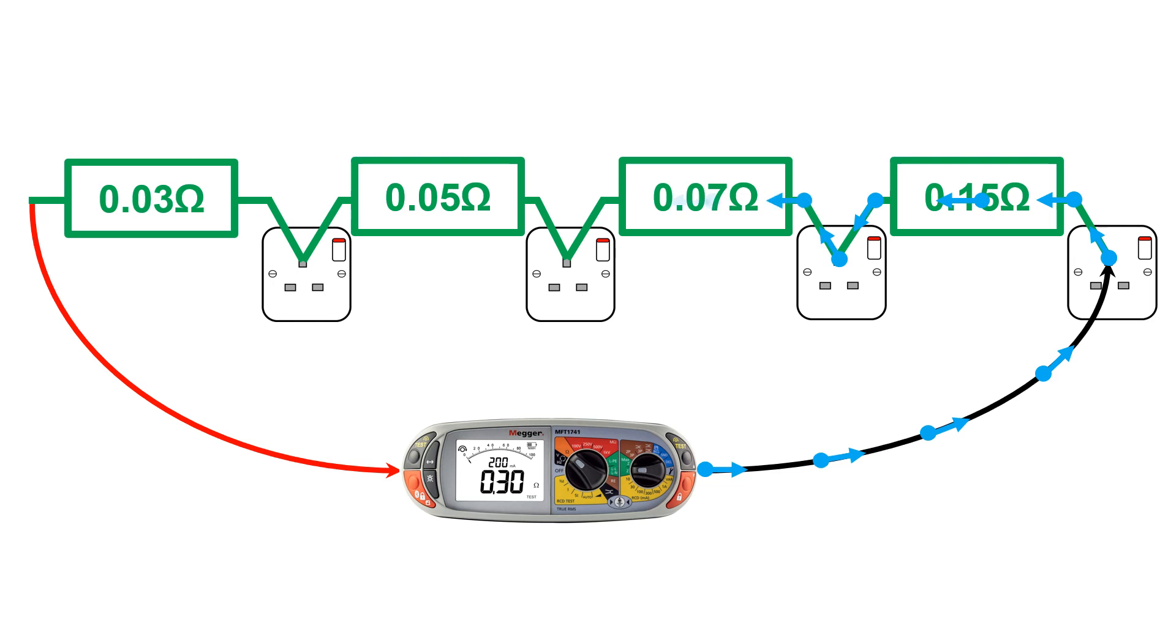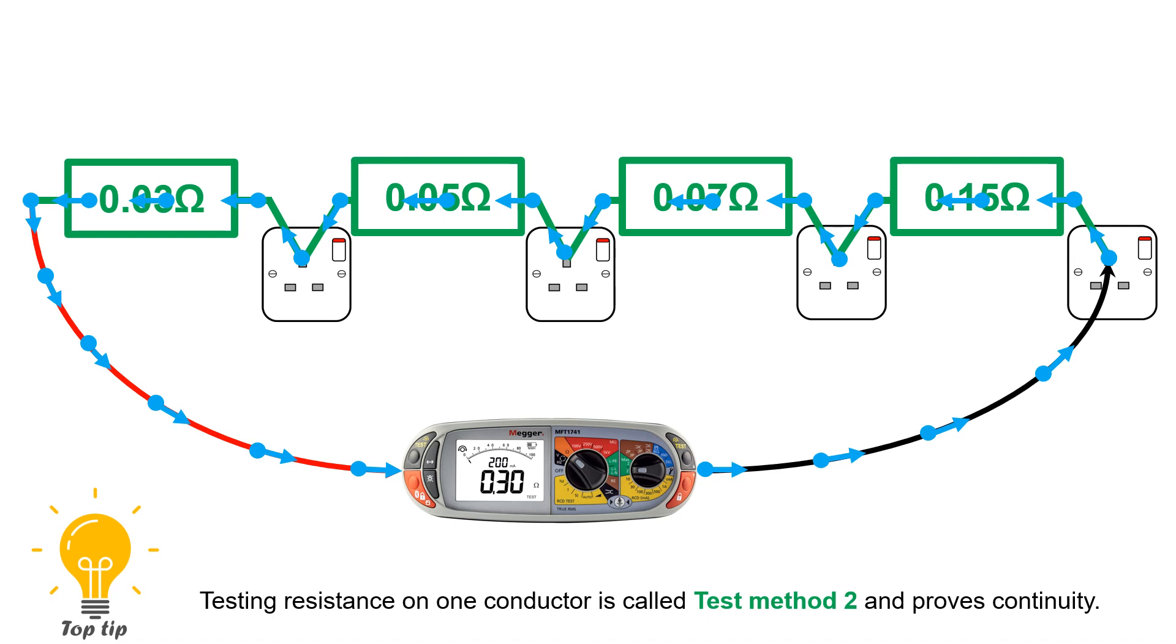those individual resistances would add up to 0.30 ohms. And if you were to test from the start of the circuit to the end of the circuit, then that total resistance would be represented on the low ohm resistance tester as represented here. When you are testing the resistance of one conductor only, we call that test method two. And this test also proves that the circuit is continuous, which is why it is called continuity.